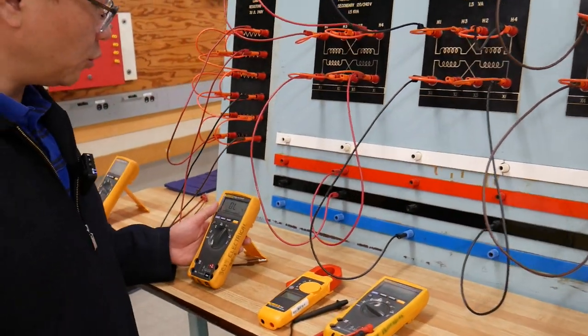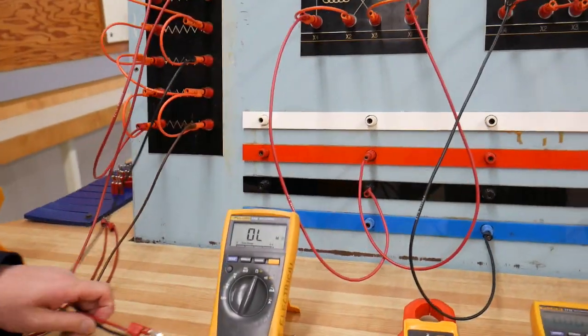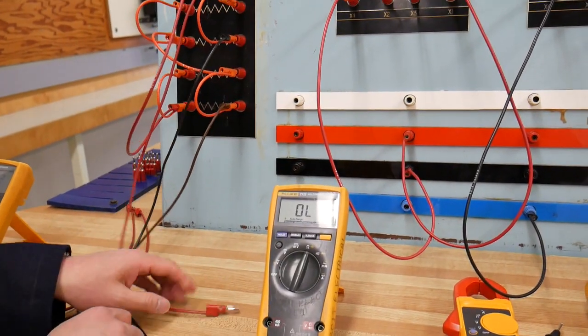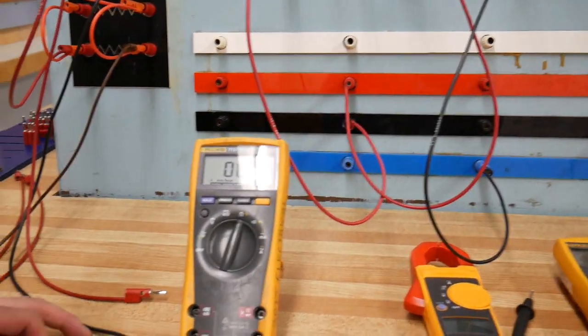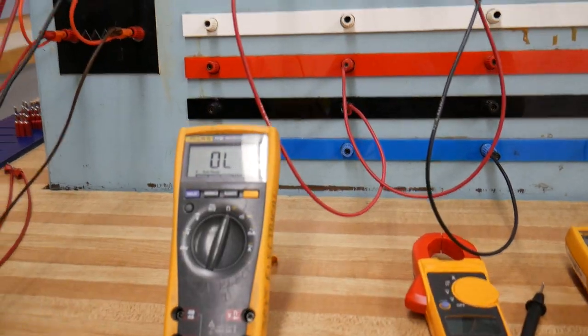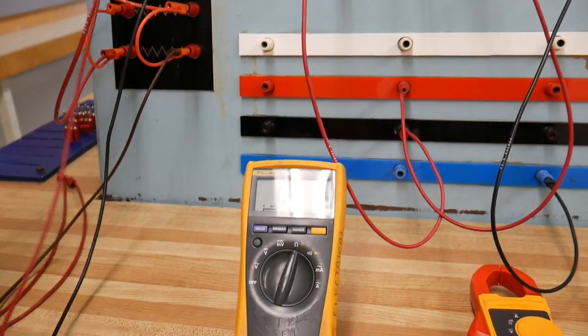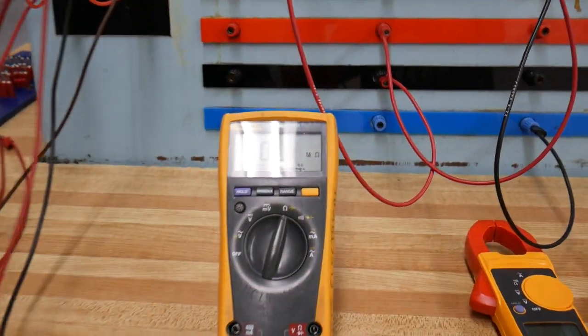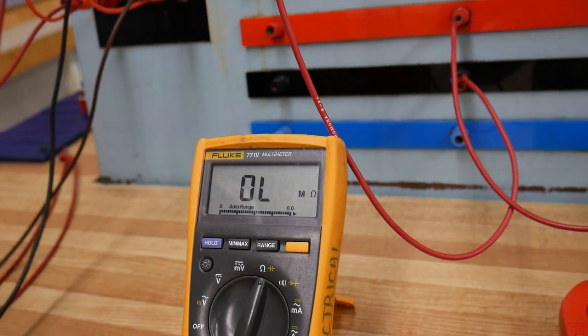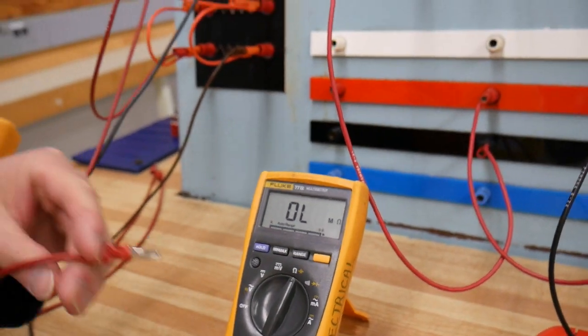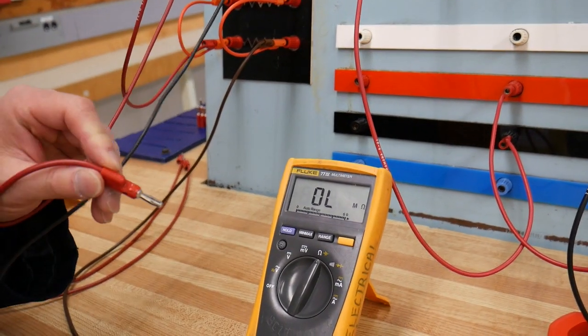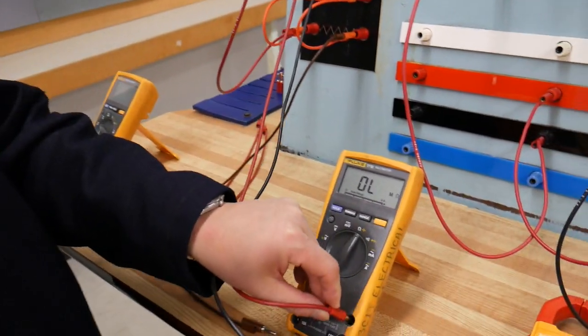Now, for the delta connected load, I also want to do some measurements. I connect my load in delta, but before I put the load into the bank, I want to measure the resistance. I have 15 ohms each, 3 loads connected in delta, so if I measure any 2 terminals, I should get a reading of about 10 ohms.